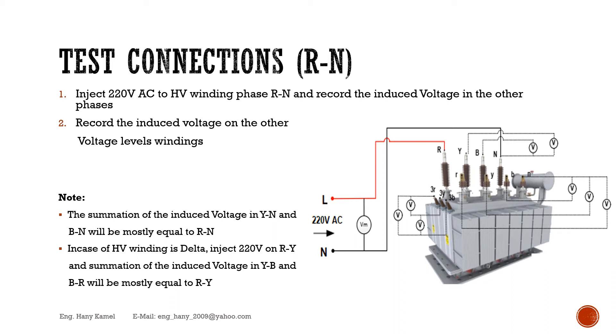Inject 220 volt to HV winding phase R-N and record the induced voltage in the other phases. Record the induced voltage on the other voltage level windings. Note: The summation of the induced voltage in Y-N and B-N will be mostly equal to R-N.